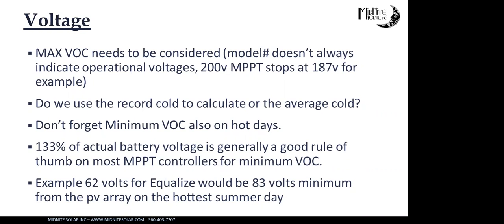The things that we get a lot of calls on every fall, we start getting calls that the batteries are being overcharged because the temperature compensation is raising the voltage on the battery. And every spring we get calls that the batteries are being undercharged. During the summer, sometimes we'll get a call where the charge controllers aren't actually waking up because the voltage is too low. And then we occasionally get calls in the winter where they're in hyper VOC or they're over voltage and won't turn on.